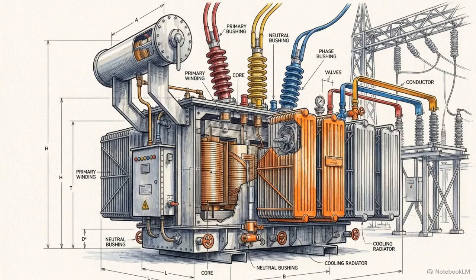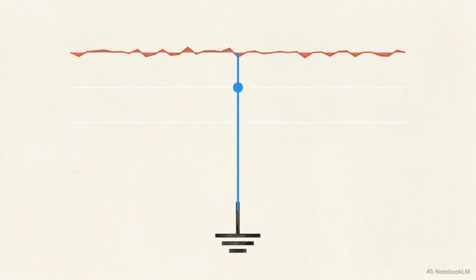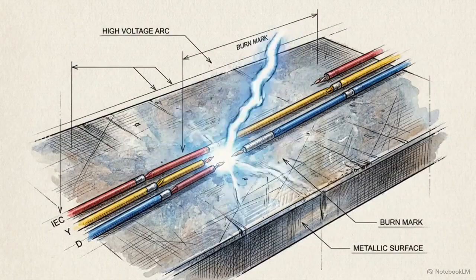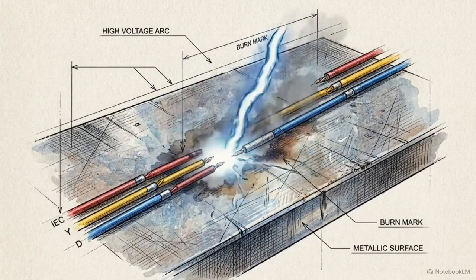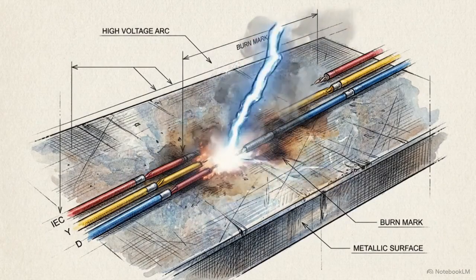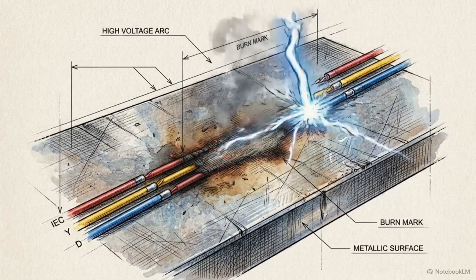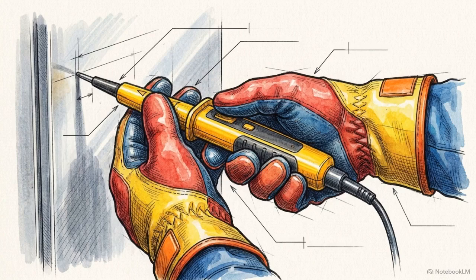Grounding transformers sit on the electrical grid as the ultimate failsafe. They provide an artificial neutral point, giving fault currents a safe, predictable path to earth when a system anomaly occurs. An ungrounded fault is a violent event. An intense arc can vaporize metal and cascade through substations in milliseconds. Rigorous, multi-domain testing forms the only barrier against that kind of systemic destruction.